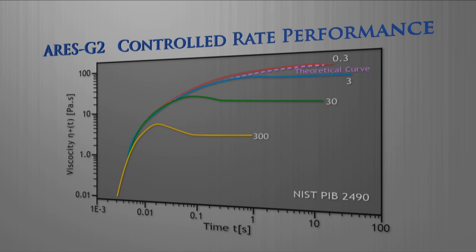The measured viscosity curves demonstrate the fast and accurate 10 millisecond motor response of the ARES G2. Time-dependent normal stress coefficient describes a material's elastic behavior. The measured curve meets the linear viscoelastic envelope at 50 milliseconds. This outstanding short-time performance is attributed to the combination of fast motor response and high transducer stiffness.